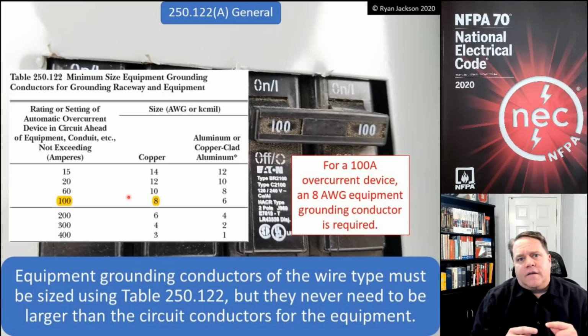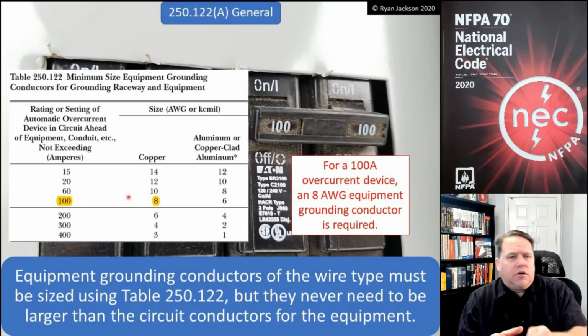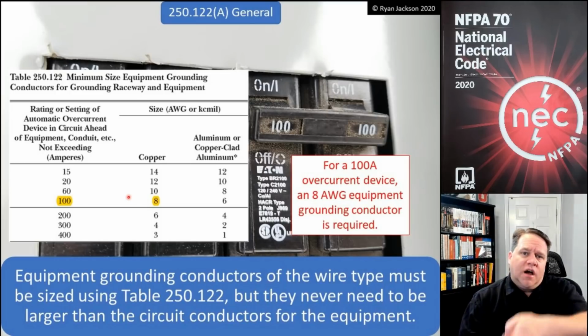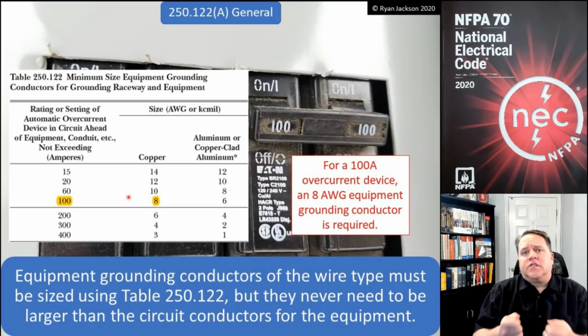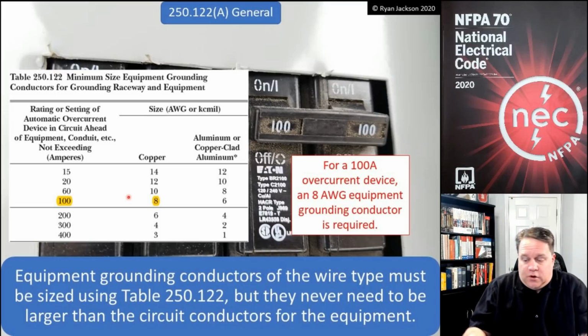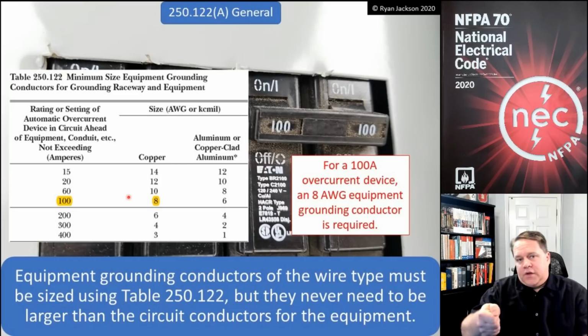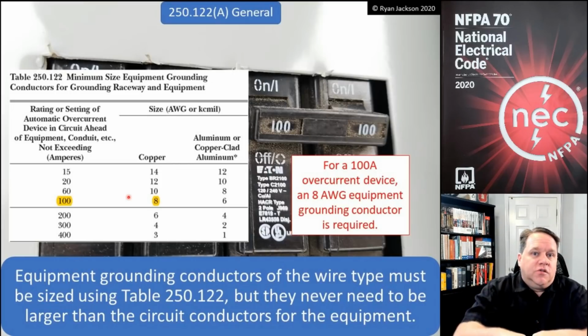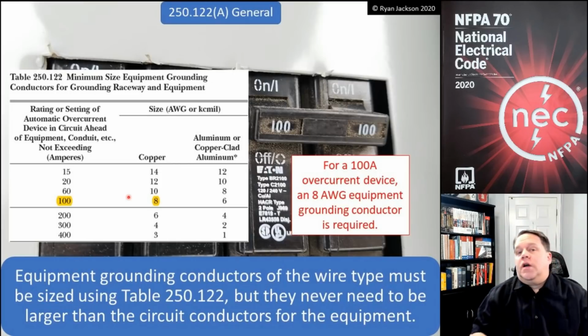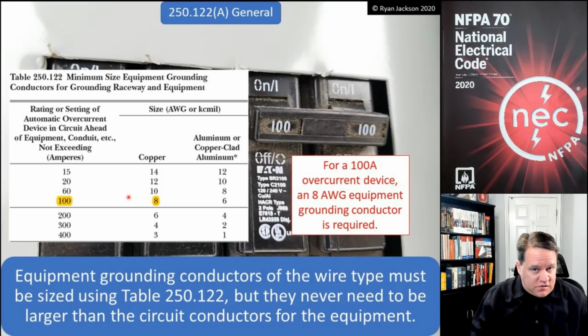So if I take the green wire and I ultimately connect it to the utility neutral, and then I connect it to the metal parts of the service disconnect, and then I take the green wire and I connect it to all metal parts that are part of the electrical installation. That means if I have a ground fault, if the ungrounded conductor, a circuit conductor, energizes the metal parts, then it's essentially a short circuit. For all intents and purposes, I'm taking the black wire and jamming it into the green wire, and that's going to have an extremely low impedance, and that's going to generate a lot of current, and it's going to trip the breaker or open the fuse.